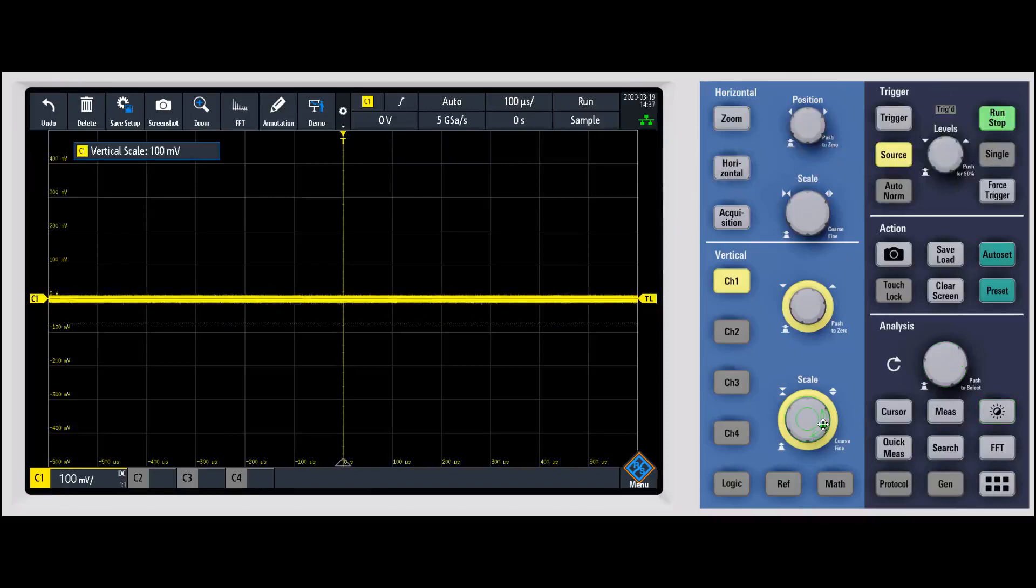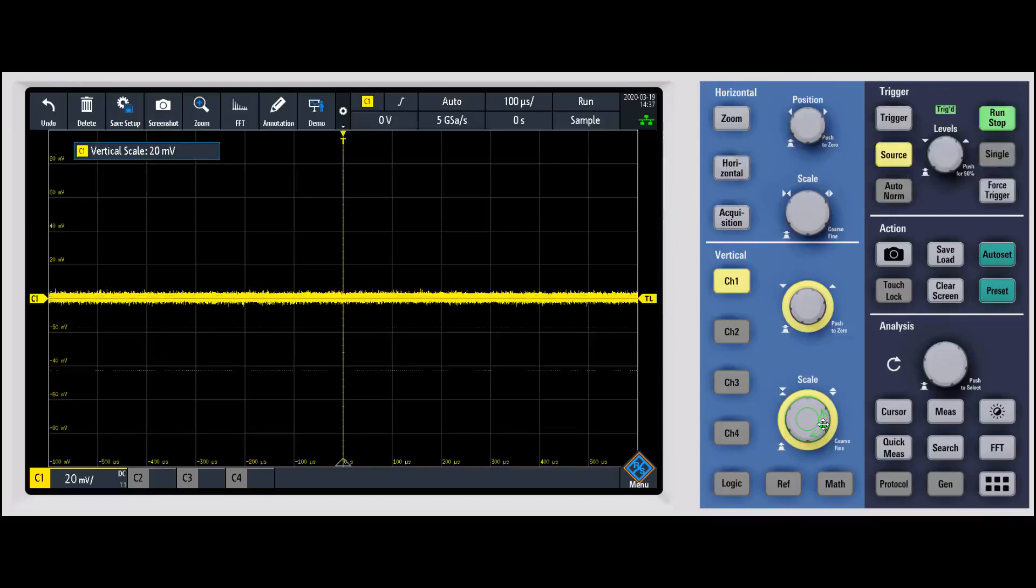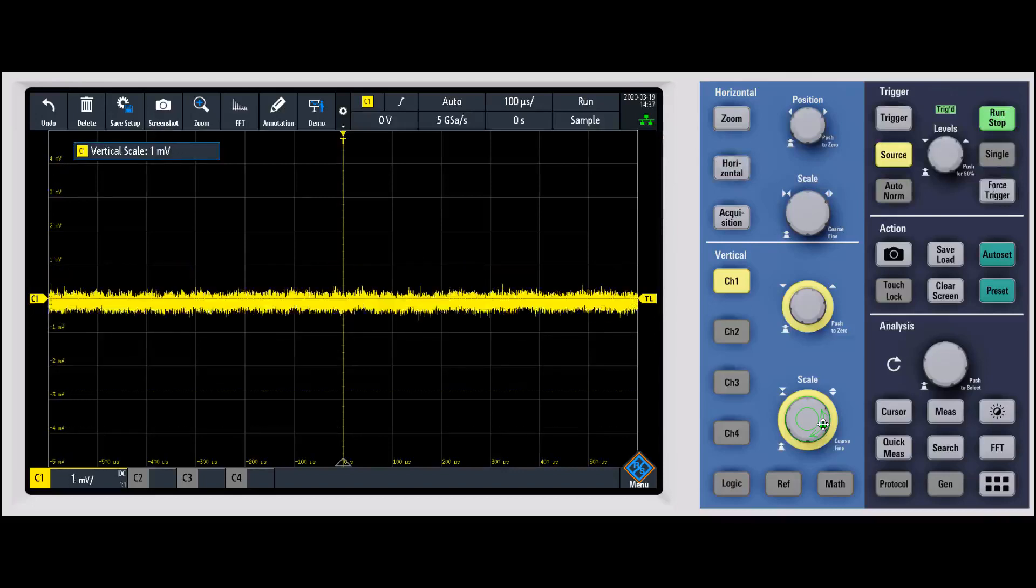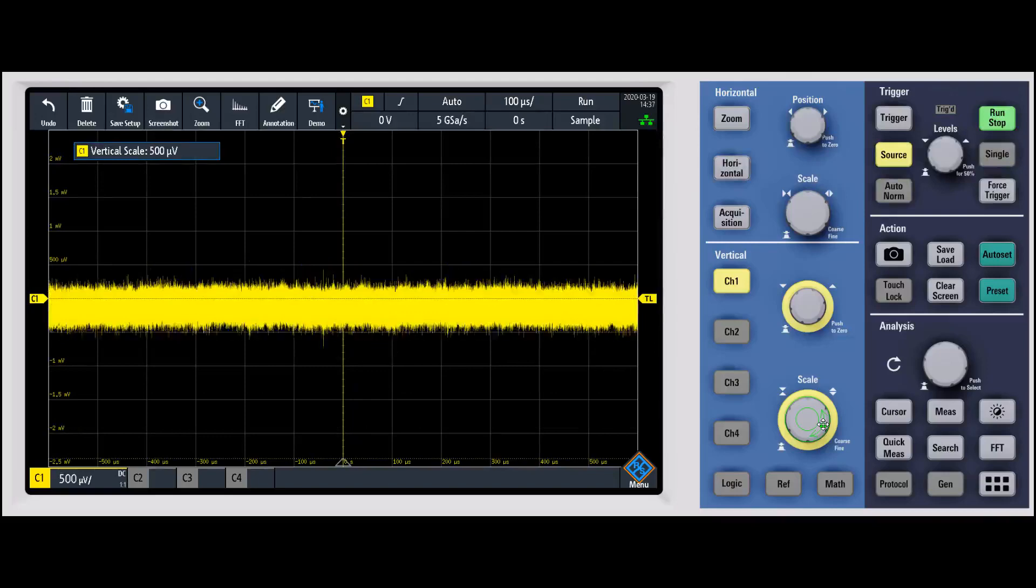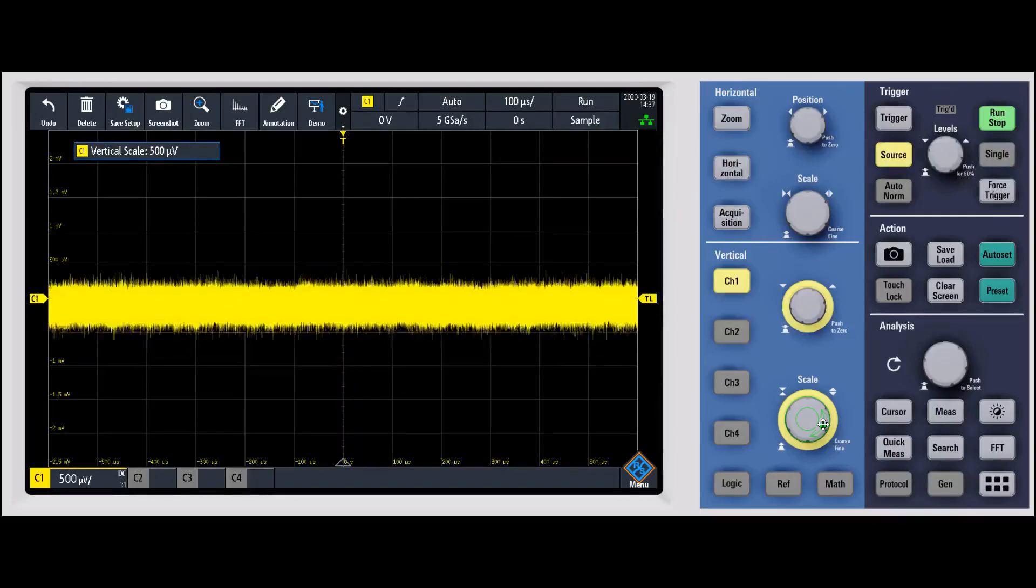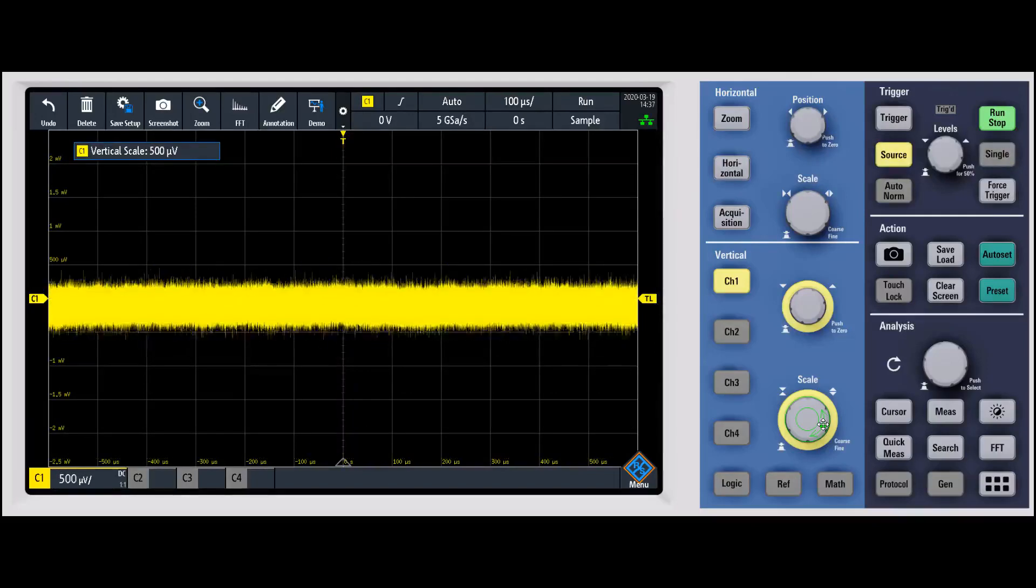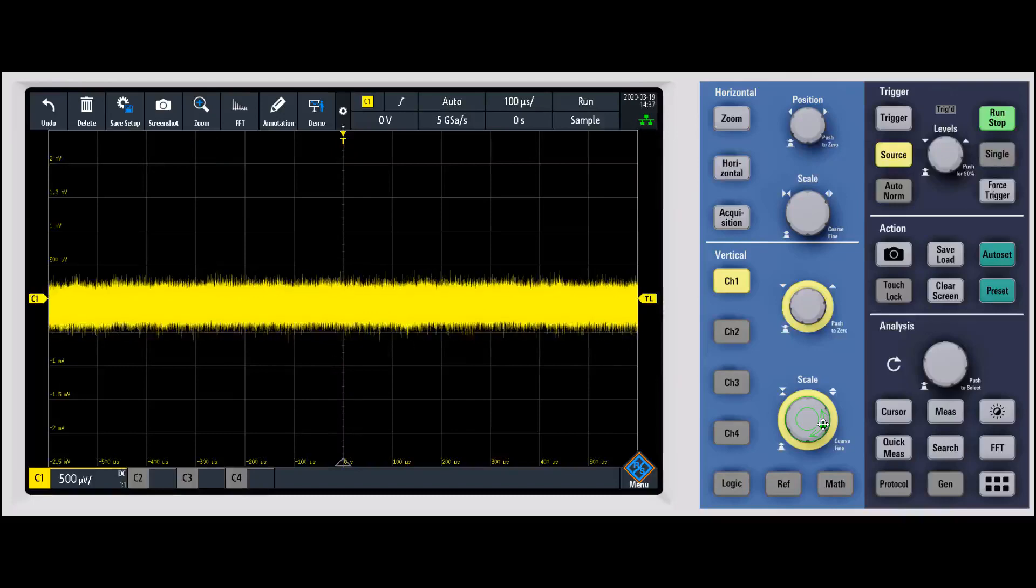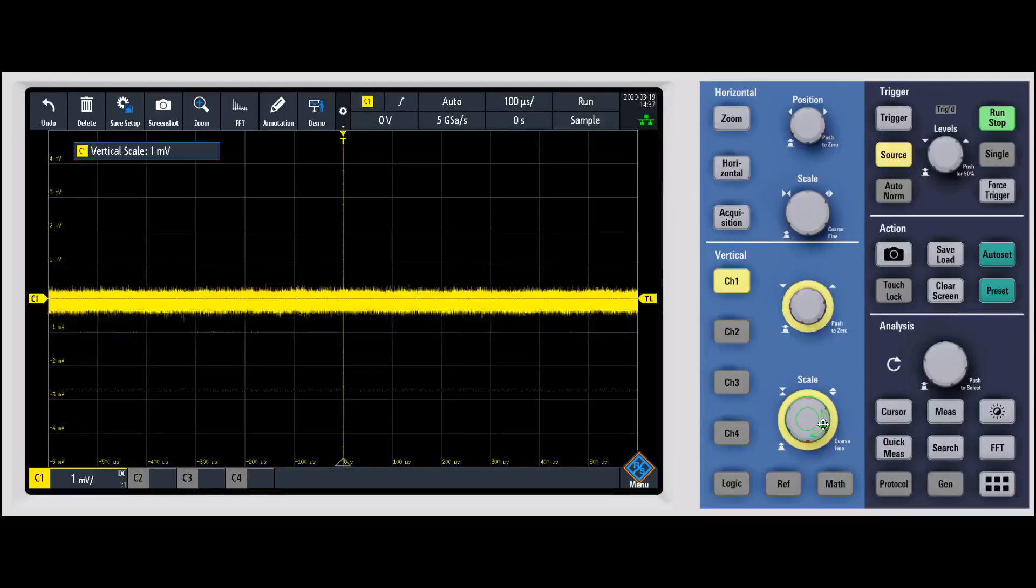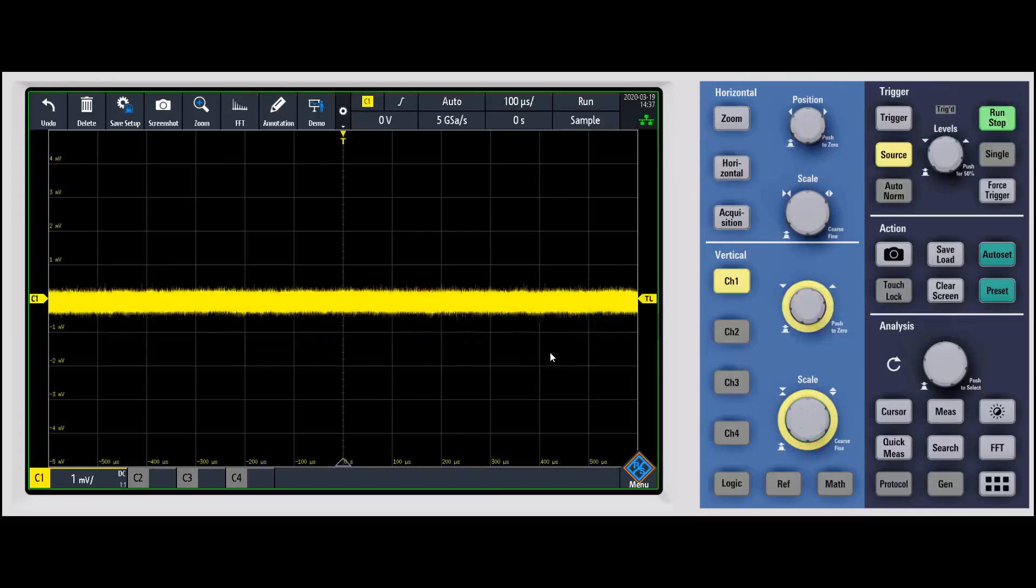We'll go down to the smallest volt per division setting on the RTM3000, which is actually 500 microvolts per division. That's lower than most oscilloscopes can do. Most oscilloscopes can do one millivolt per division, so we'll set it to one millivolt per division.